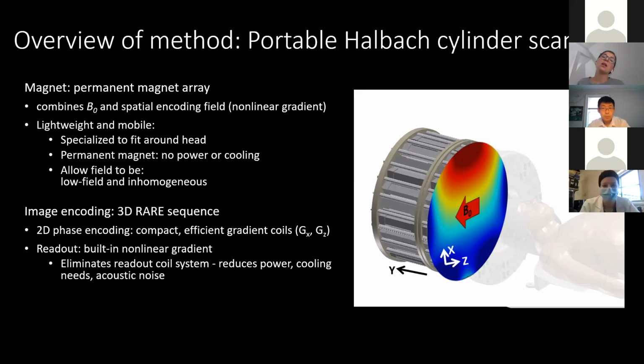To do the image encoding, we use 3D RARE sequences, which use a train of spin echo pulses. We do 2D phase encoding with compact, efficient gradient coils that are built into the system. But the readout encoding, which is generally the most power-hungry encoding field of the MR system, is created with a built-in nonlinear gradient in the permanent magnet. So no additional coils or amplifiers are needed for that encoding field. That's called the readout field, and using the built-in readout in the permanent magnet eliminates the coil system. This greatly reduces the power and cooling needs of the scanner, and also very much reduces the acoustic noise that anyone who's ever had an MR scan is very familiar with.